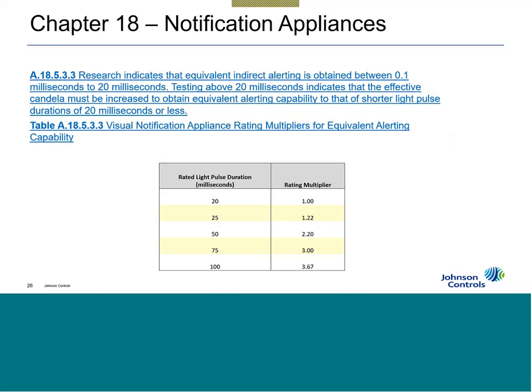Do a 1-for-1. Johnson Controls Autocall LEDs, we're around the 9 millisecond pulse width. Plenty of room in there. We actually lobbied as a company to make it 10 milliseconds, not 20. So you don't have to worry about this whole derating thing when you use Johnson Controls Autocall LEDs. Doesn't affect us at all. But if you're using some of the competitor products that are out on the market today, not all of them, but some of them are running 80 millisecond pulse width.